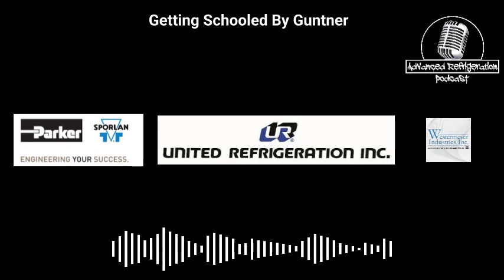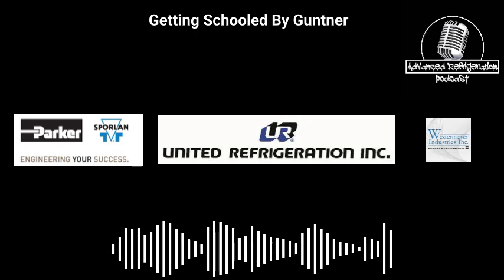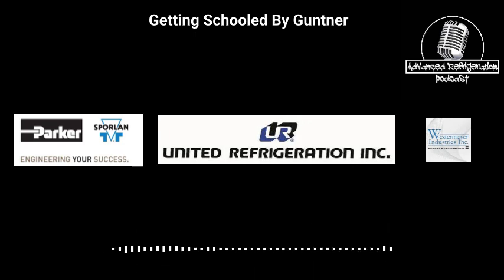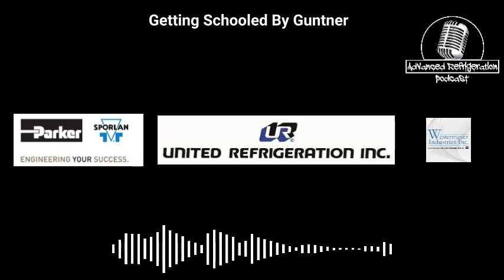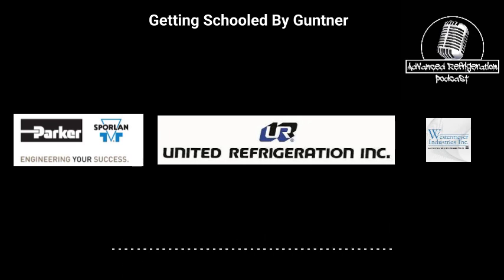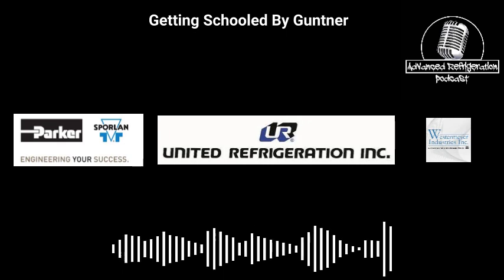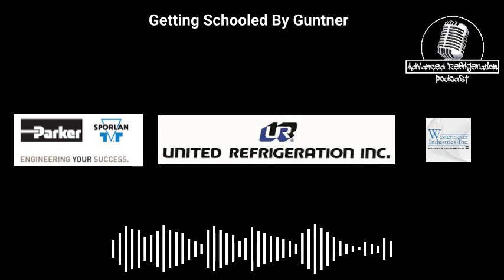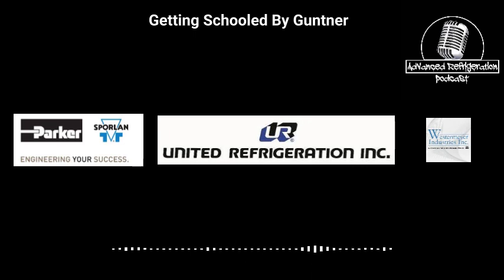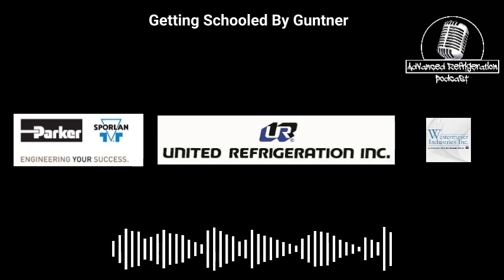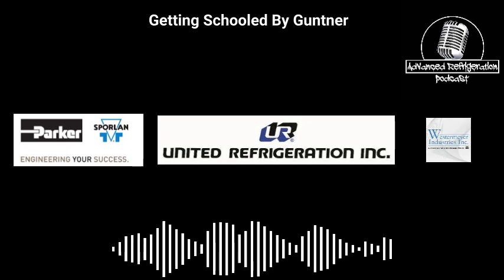You're going to stump me on this one, because that's a project one of my colleagues actually worked on, and I should know this answer. These fans use a 0 to 10 volt signal to maintain the speed. But by using the resistors and only using that 10-volt signal, you're able to control the speed to make it reach a certain maximum RPM. Does that make sense? Yeah, so they're basically faking out the signal by using the resistor to bleed it down.